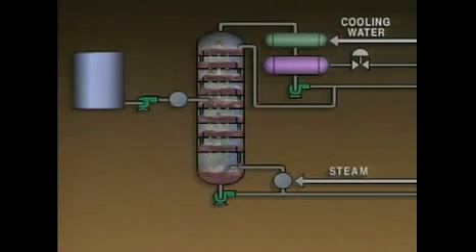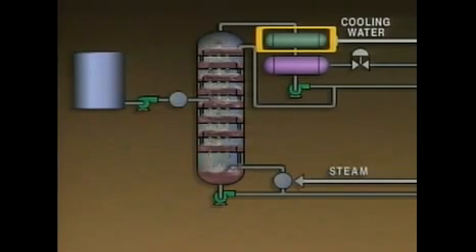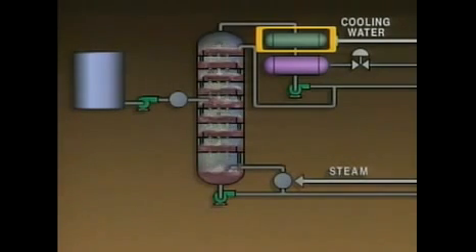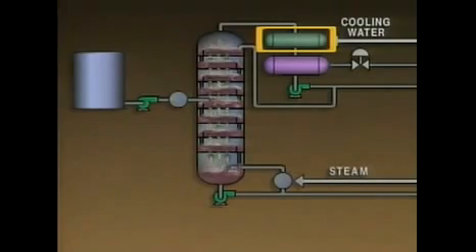Another problem that may affect the tower's differential pressure is a decrease in condenser efficiency. If the condenser's tubes are plugged or there's not enough cooling water flowing through the condenser, the condenser's pressure will increase. As a result, the flow of vapors from the tower to the condenser will decrease, and so will the vapor flow up the tower. This means that the tower-top pressure will increase and the differential pressure will decrease. If a condenser problem is suspected, the condenser should be checked and corrective action should be taken if necessary. Changes in the tower's differential pressure may have other causes in addition to the ones identified, so it's important to carefully evaluate any situation before corrective action is taken.